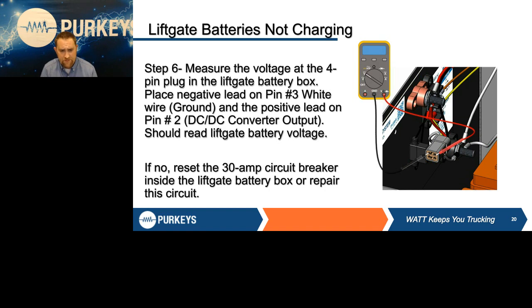If you don't get any voltage here, then you want to follow this circuit back to the liftgate batteries. The next connection in line is a 30 amp circuit breaker. Make sure that 30 amp circuit breaker is not tripped, and that you have a good path to those liftgate batteries.